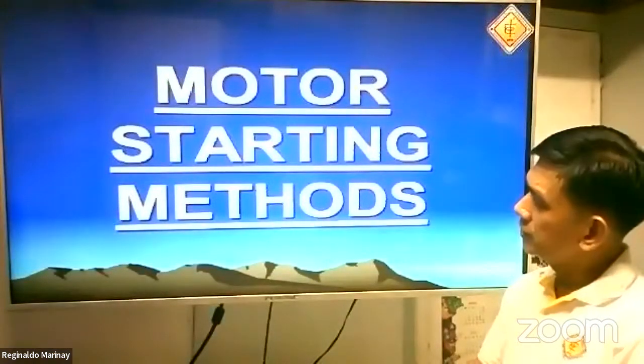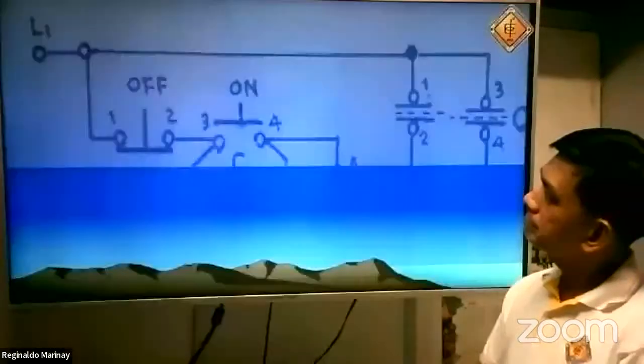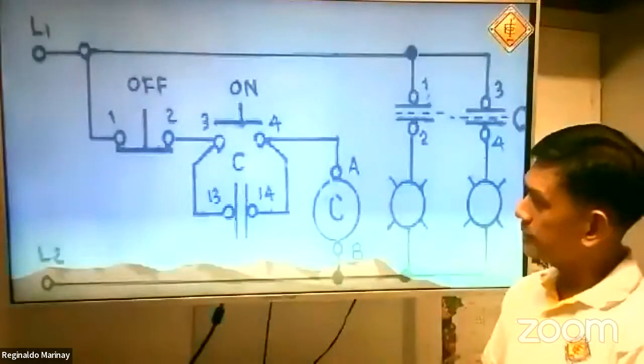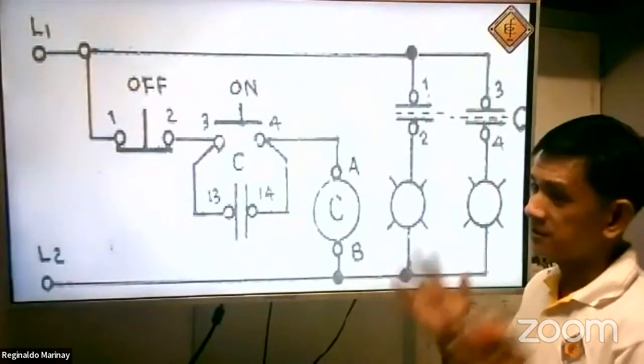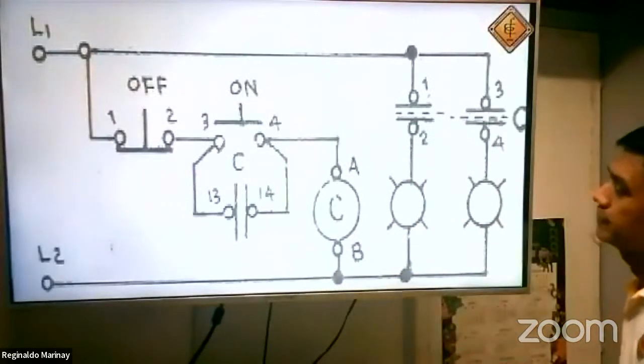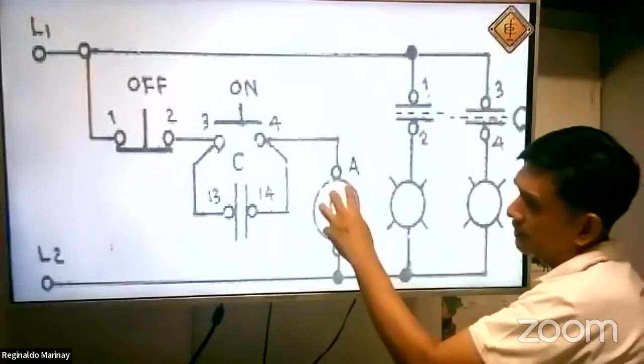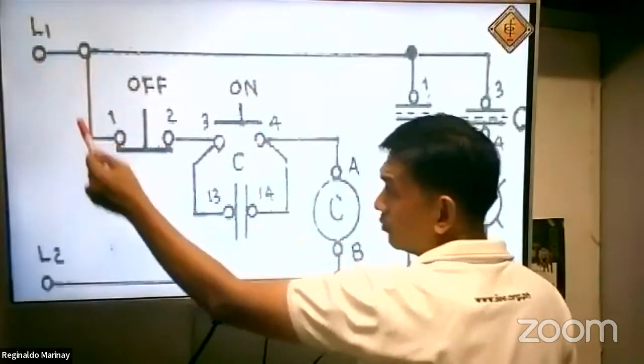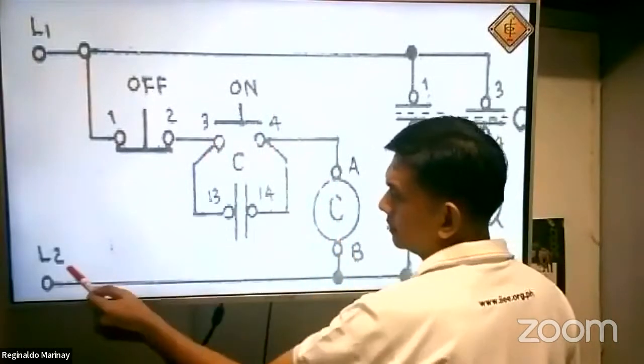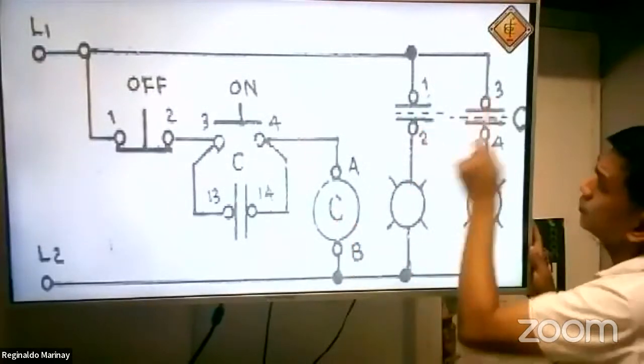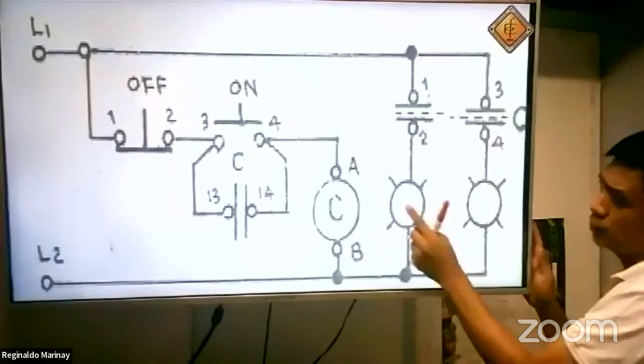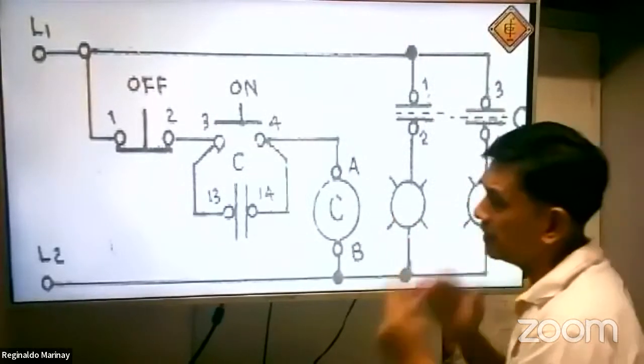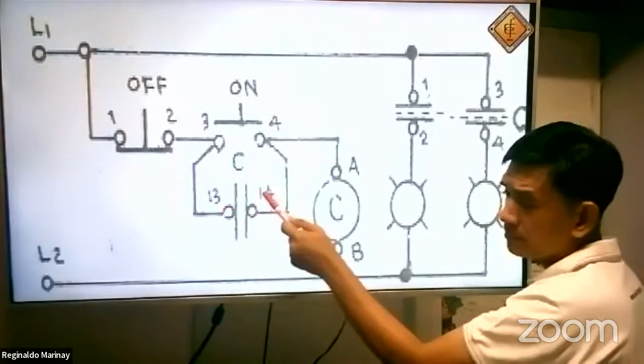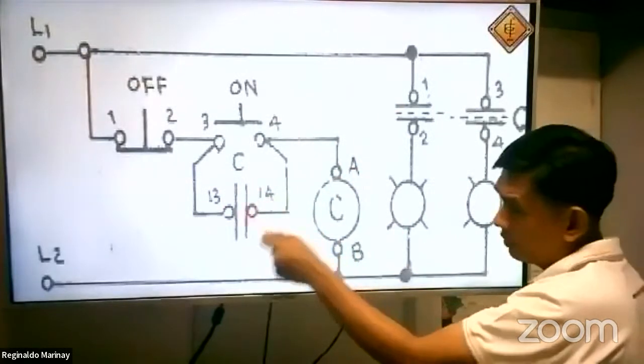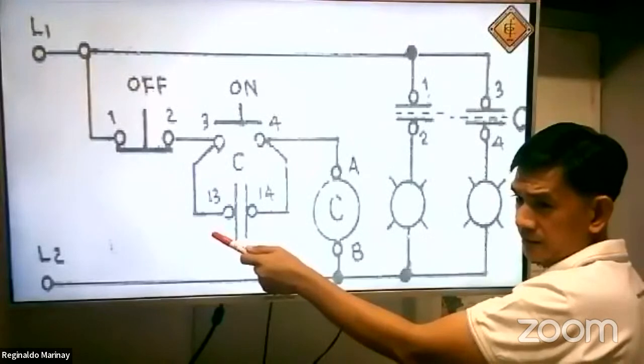Okay, this is the basic operation of a magnetic contactor or relay. This is the heart of the operation of the magnetic contactor. Take a look here. This is the holding coil of the magnetic contactor. Once we press this push button down, the current will flow from line 1, energizing your holding coil C. Once this becomes energized, 1, 2, 3, 4 will become closed, energizing your 2 lamps. Okay? And also at the same time, this auxiliary contact 13 and 14 will become closed. That will become closed. Okay, are you still aware? So that will become closed.